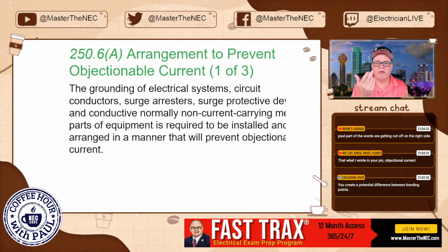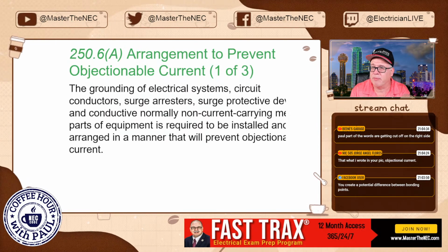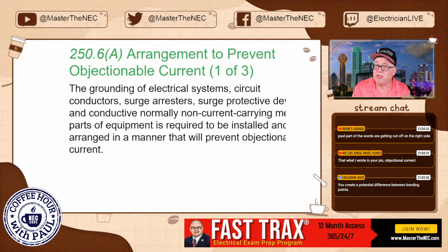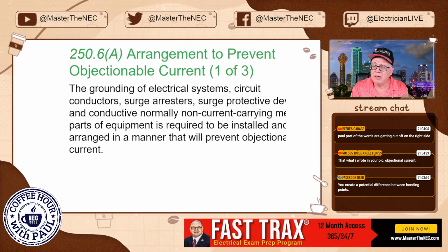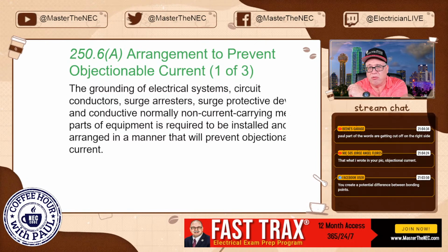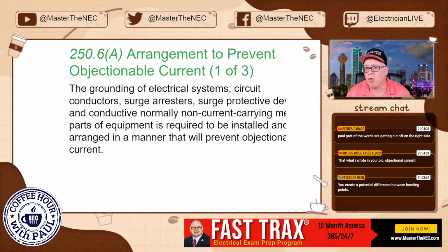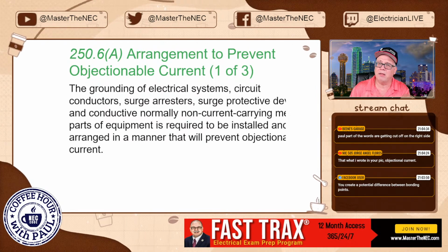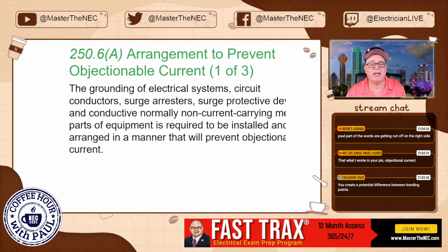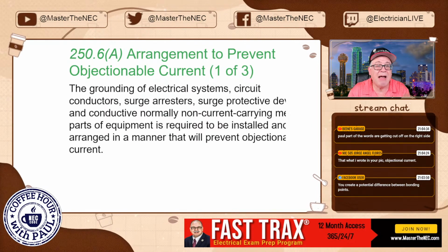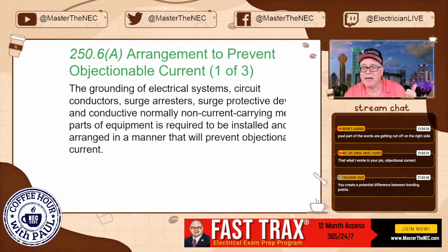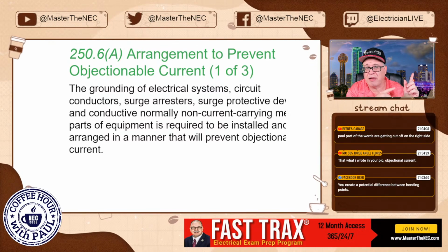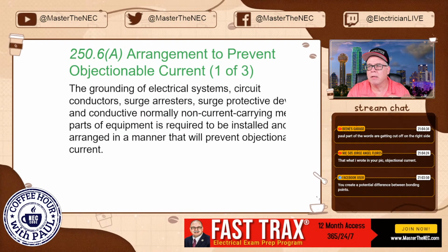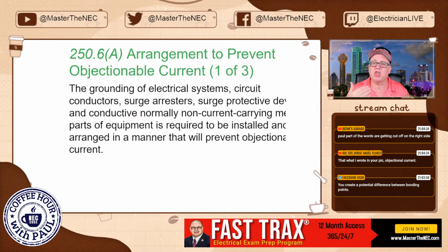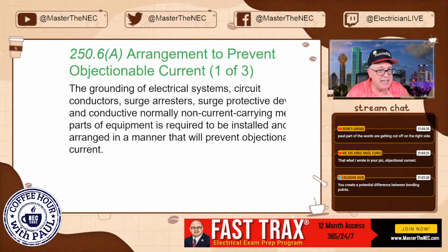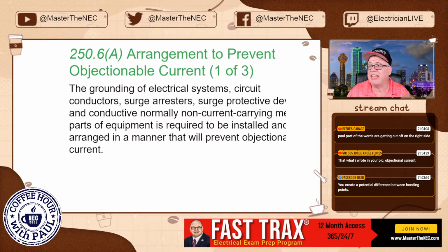Now, one of the things that's interesting for everybody that hates AFCIs, arc fault circuit interrupters: we get a lot of things that people refer to as nuisance tripping when you put an AFCI in, and they want to blame the AFCI. And again, it's not without some issues with those devices, but the reality is the majority of those issues are when people push things back in the box, and now the grounded neutral conductor comes in contact with the equipment ground. Now, that won't necessarily clear an overcurrent device on a standard breaker, because they both go back to the source, to the same location. So that won't necessarily clear anything. But it could put current traveling on a path that wasn't intended. So an AFCI can detect this.